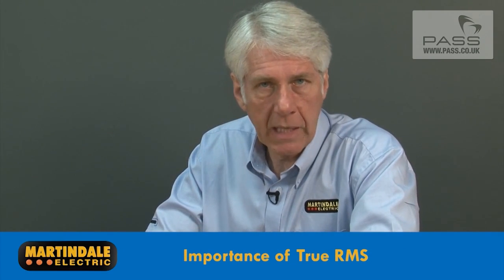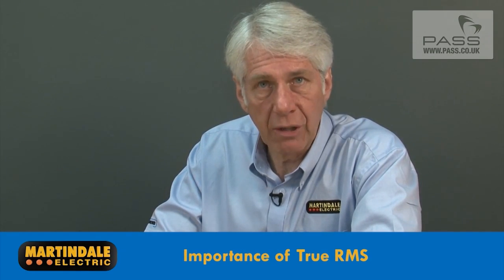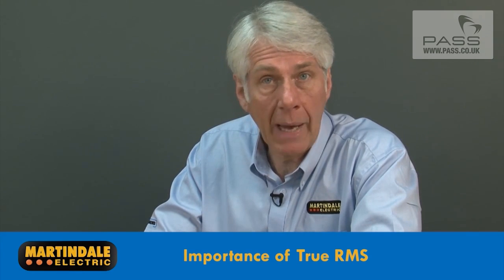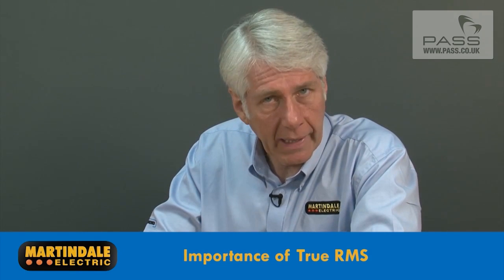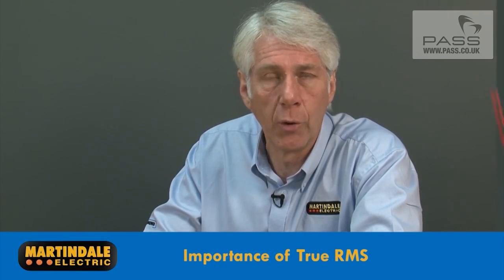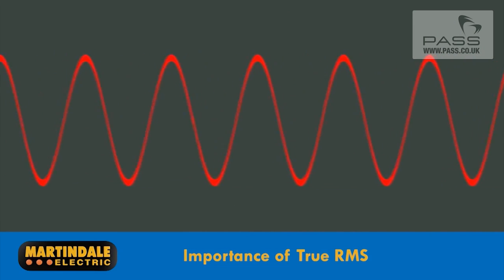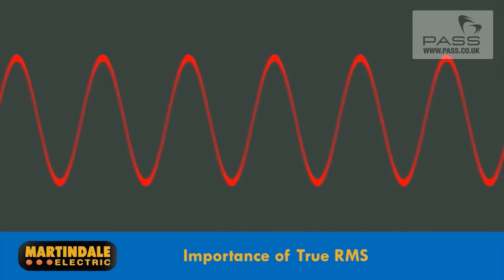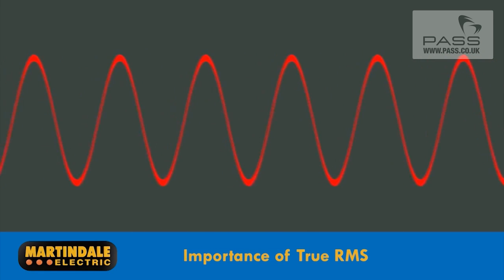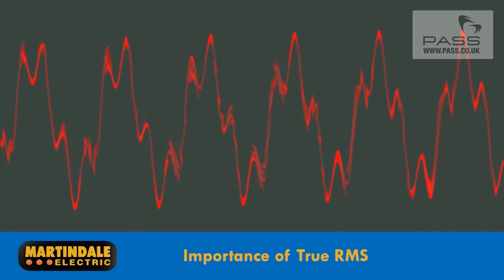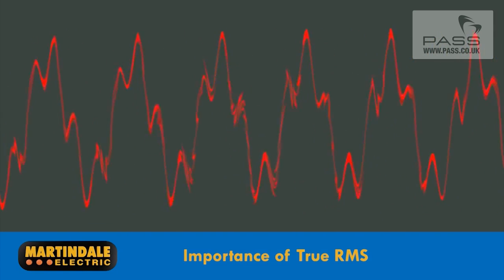True RMS is becoming even more important with the increased use of modern low-energy lighting systems and power supplies, which generate harmonics and cause distorted current waveforms. Basic clamp meters without True RMS capability are calibrated for the measurement of sine waves only and will give large errors on distorted current waveforms.